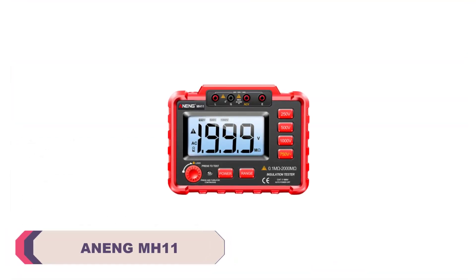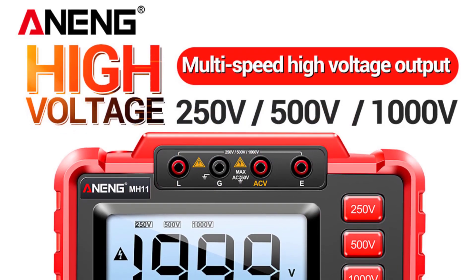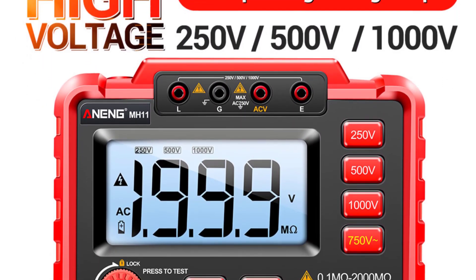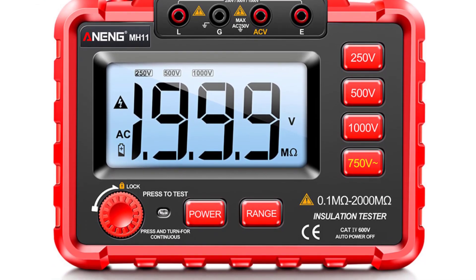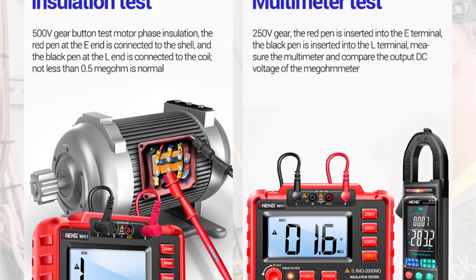Number 4: ANENG MH11 Digital Megohmmeter. One of the standout features of the ANENG MH11 is its impressive measuring range of 0.1MΩ to 2000MΩ. This wide range allows testing of a variety of electrical components, circuits, and systems with confidence. The ability to choose from testing voltages of 250V, 500V, and 1000V further enhances its versatility, ensuring accurate readings across different scenarios. The MH11's consistent performance has been a highlight, with an operating range of 0°C to 40°C delivering reliable results whether working indoors or outdoors.